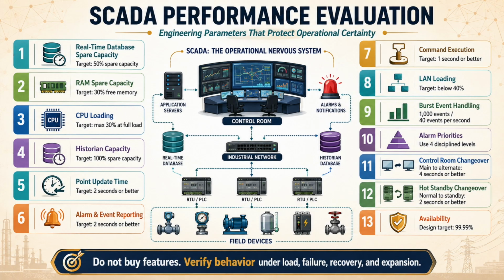The 18th engineering parameter is standby to normal recovery, because the recovered primary may have missed alarms, acknowledgements, commands, historian values, communication changes, and operator actions. It must not simply return, it must return correctly, reconcile state, and avoid resuming authority blindly unless the operating philosophy allows it safely.